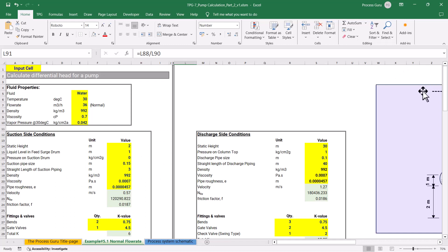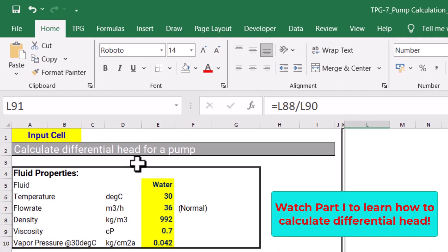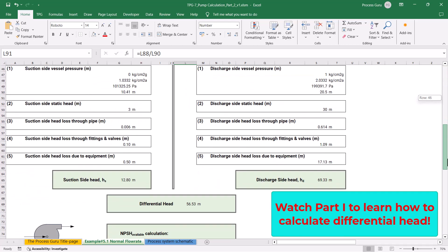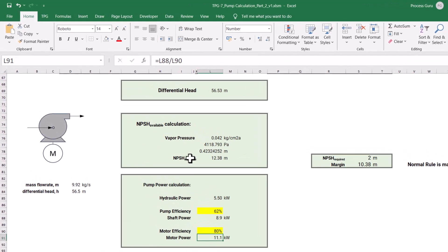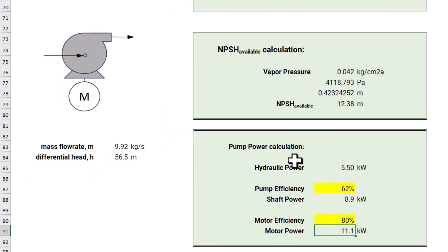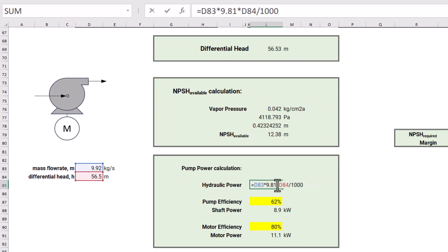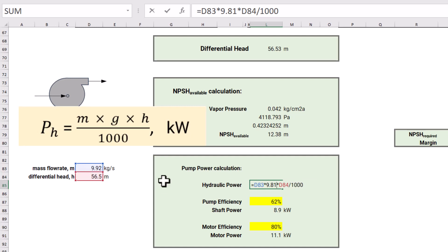Let's solve this example on the Excel platform. This is the same Excel sheet used in my previous video for differential head and NPSH available calculations. We will now extend that example to calculate pump power. The mass flow rate is 9.92 kg per second and the differential head is 56.5 meters. Using the hydraulic power formula — mgh divided by 1000 — that is 9.92 × 9.81 × 56.5 ÷ 1000, we get 5.5 kilowatts.